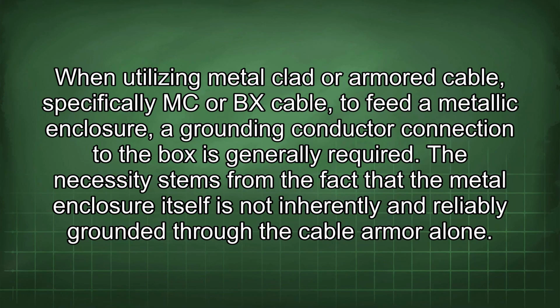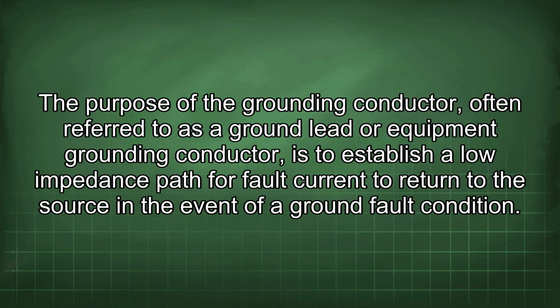When utilizing metal-clad or armored cable, specifically MC or BX cable, to feed a metallic enclosure, a grounding conductor connection to the box is generally required. The necessity stems from the fact that the metal enclosure itself is not inherently and reliably grounded through the cable armor alone.